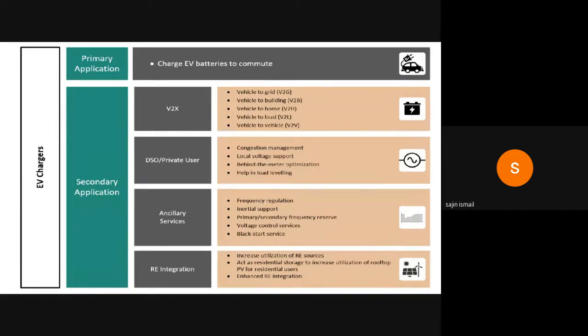Then there are ancillary services, which are basically frequency regulation. In a grid, whenever the demand for power is high or low, the generation has to be controlled - the governor of a generating station plays a major role here. The frequency should be maintained within limits accepted by the grid code or grid operators. If it varies beyond that, it's not acceptable. It should be maintained at a particular level, like 50 hertz, with some accepted variation, but it shouldn't vary beyond that.